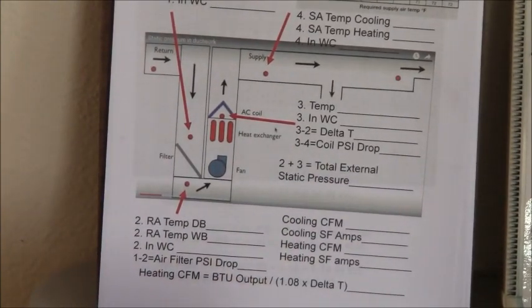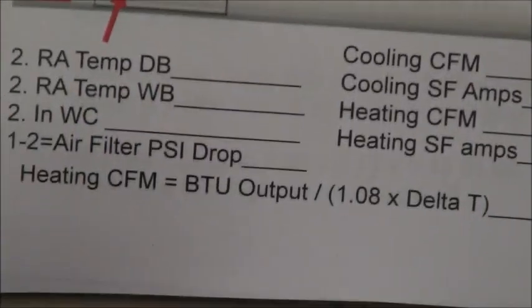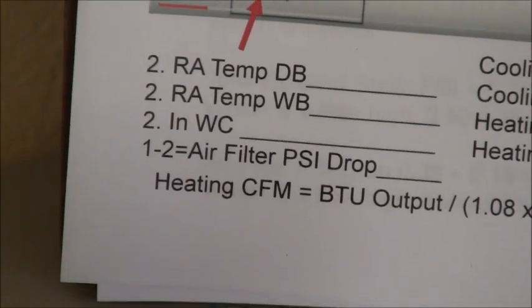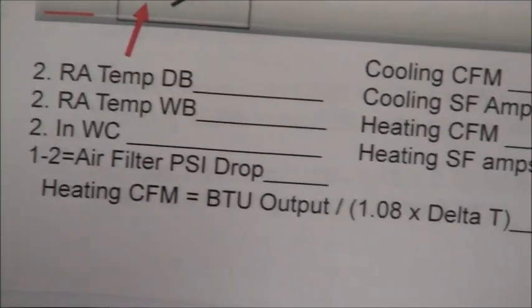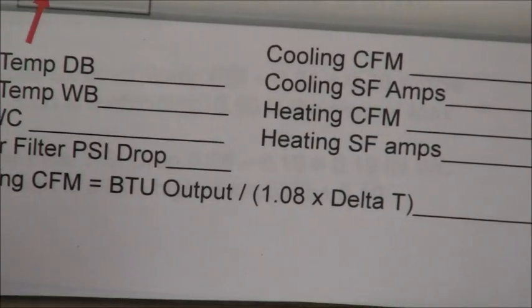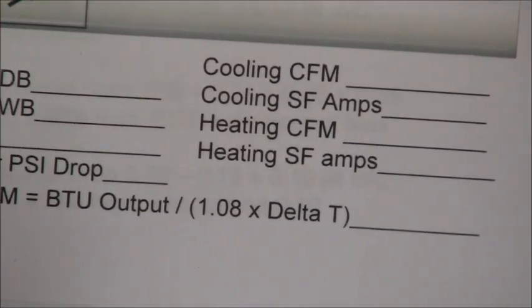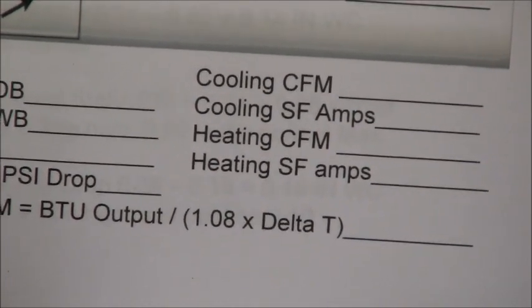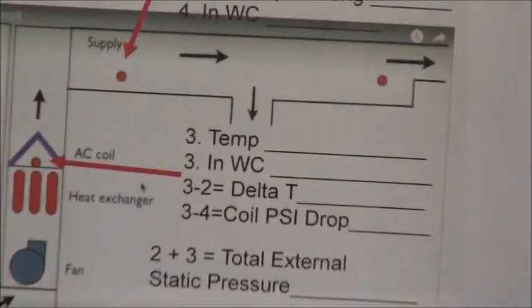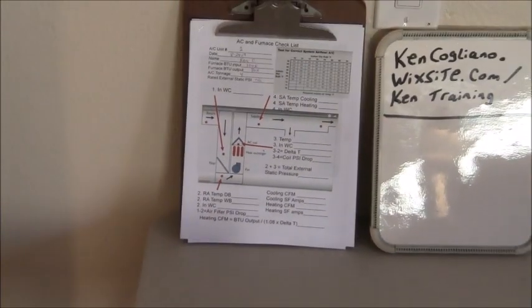To get the heating CFM, you can see here: heating CFM equals the BTU output divided by parentheses 1.08 times the delta T. We'll go through all that so you get exactly what it is — your delta T is right there once we fill that out. So we'll go through this entire checklist.